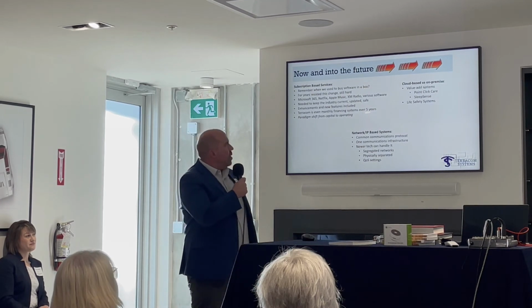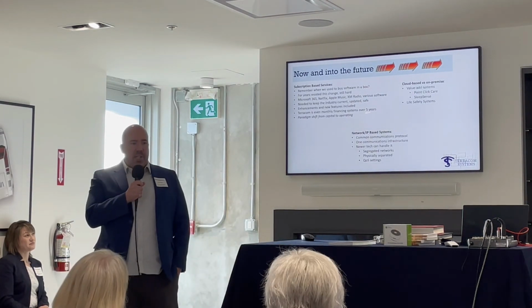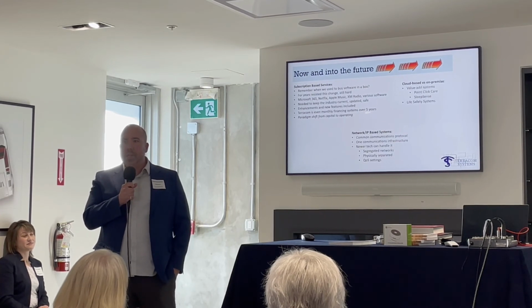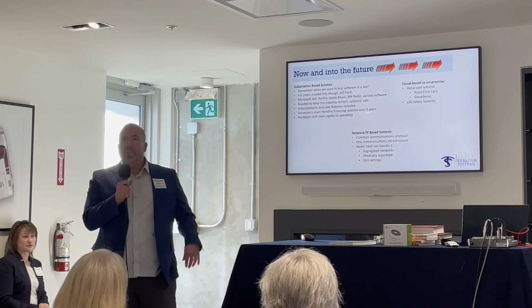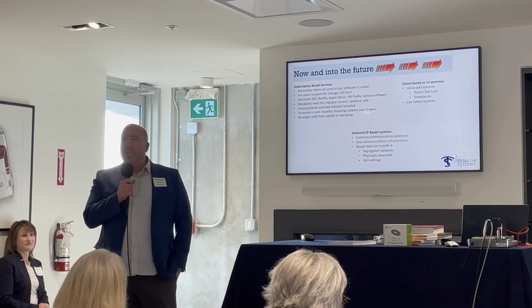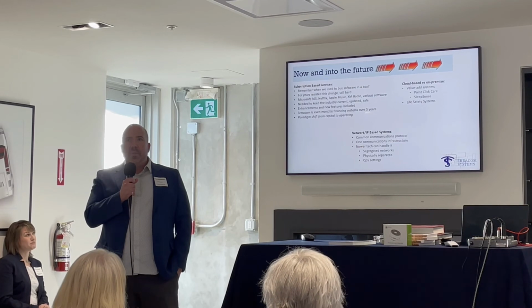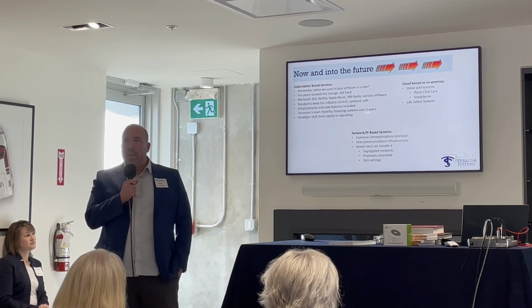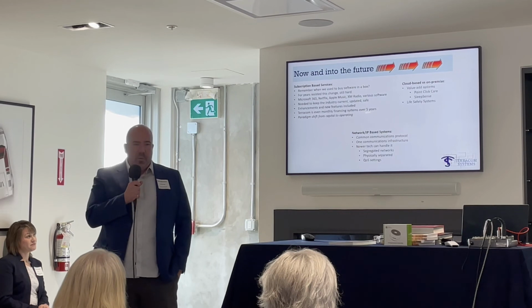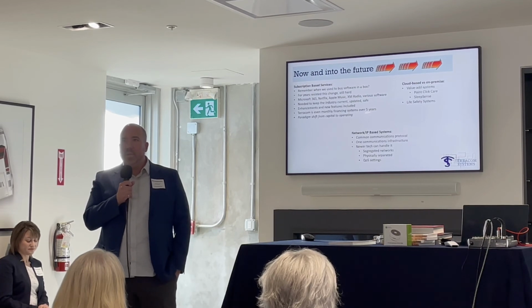What else here? With regards to cloud-based and on-premise systems I was talking about earlier, one thing I feel very strongly about, as you can tell, is life safety systems, the systems that enable your residents to request assistance, whether by pressing a pendant, a call bell button, or a pull cord in a bathroom. That stuff really needs to be on premise. All that electronics, hardware, and software, most proper systems out there with the certifications, UL 1069 or UL 2560, they all reside on premise. They all will work if the phone lines are severed, or if the network internet is severed. You will still get those calls through to your carer's wireless phones.